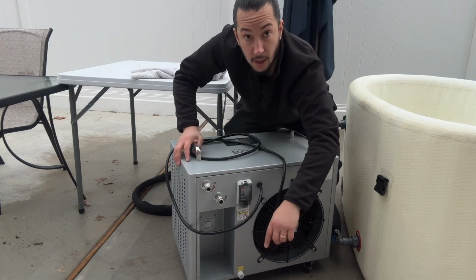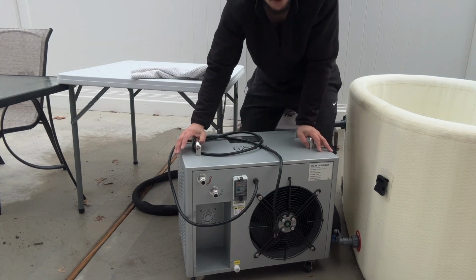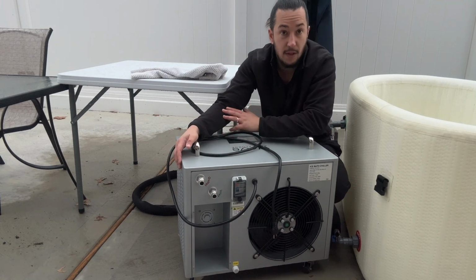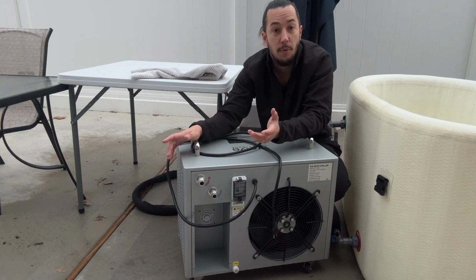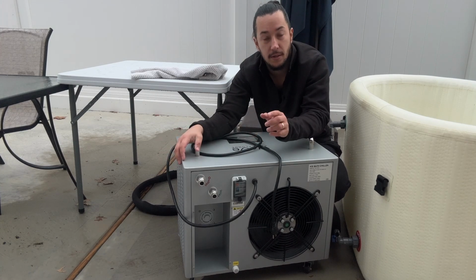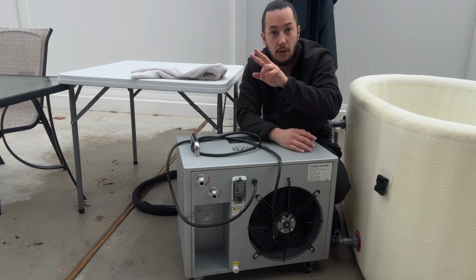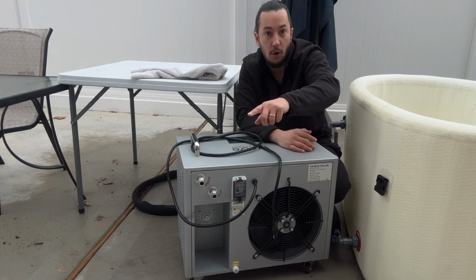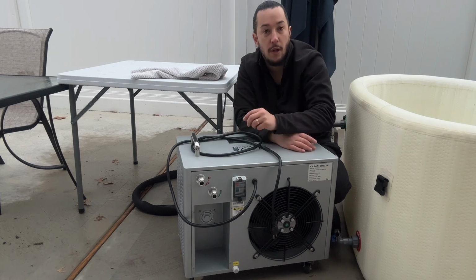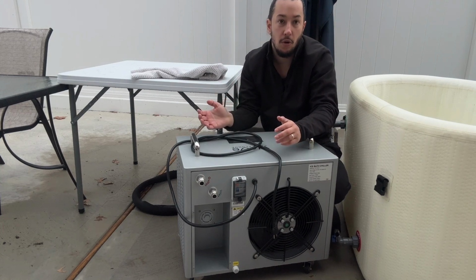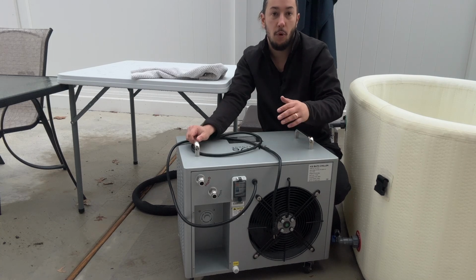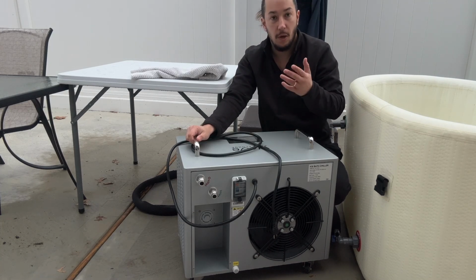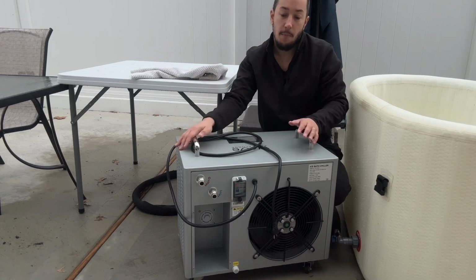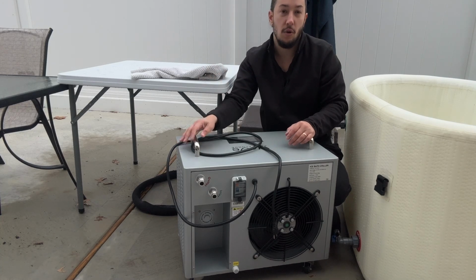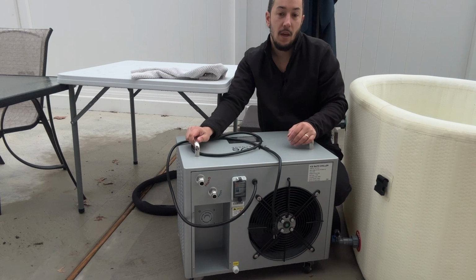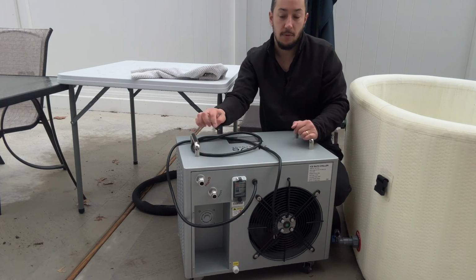We also have a low point drain. A lot of chillers don't have that, and I don't know why, because to me it's such an obvious addition and not super hard to do. As we engineered the water system, we figured out a place for a Y connection at a low point, with a hose to that connection. You unscrew the cap, and when storing it you can tilt it, which helps drain all the water out, since there's a lot of water in this chiller-- hoses, cavities, and parts that store water. That helps drain it so you don't get mold growing in the system, and you don't get water leaking and causing damage. So that's the low point drain.